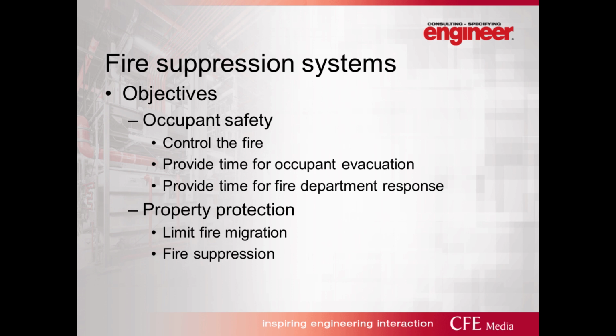The second objective is property protection. Obviously, this is very important to everyone as well. Occupant safety always comes first, but property protection is very important. You want to, again, try to limit that fire size as best as you can so that it doesn't migrate to other areas of your building and get to the point where it can't easily be suppressed either by a fire suppression system or extinguished by the fire department. Fire suppression, which is something that many fire suppression systems actually do, is very important for property protection because, again, you're trying to catch that fire early, knock it down, and then, if you can, suppress it. Some fire suppression systems are specifically there to control the fire. Other fire suppression systems are actually there as a suppression system. They're intended to extinguish the fire.